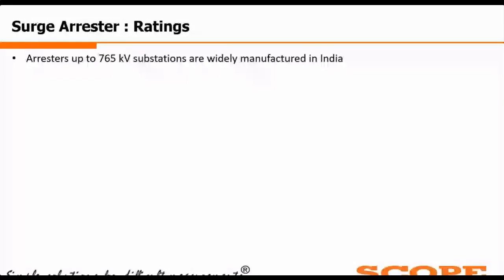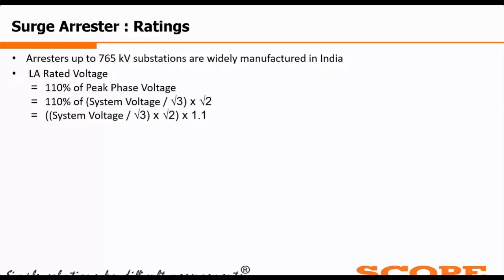Now coming to the surge arrestor ratings. Generally, surge arrestors up to 765 kV are widely manufactured in India, though some companies have started manufacturing even the 1200 kV LAs. Now, LA rated voltage is considered as 110% of the peak phase voltage. 110% of the peak phase voltage means system voltage divided by root 3, multiplied by root 2 to get the peak voltage, multiplied by 1.1. That is the LA rated voltage.